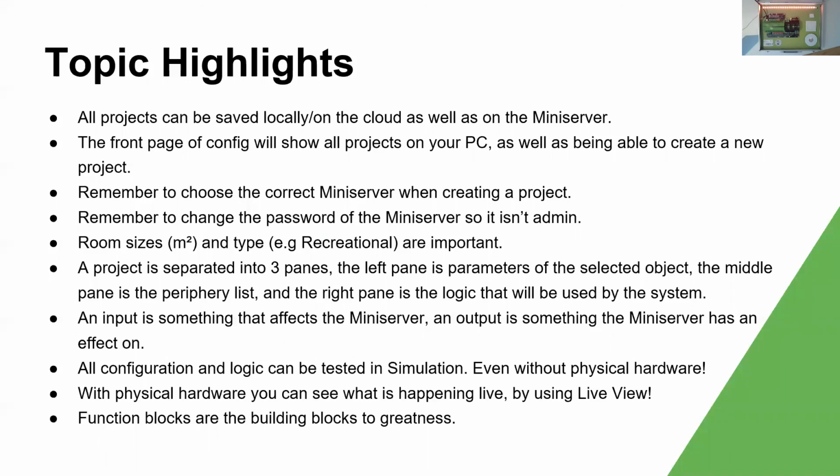Remember to choose the correct mini server when you create a project. Don't choose a Go if it's a Gen 1. Don't choose a Gen 1 if it's a mini server. Remember to change the password from admin. Really, really important. Room sizes in meters squared. Really, really important for the heating logic later on.